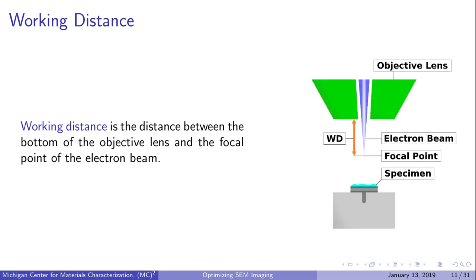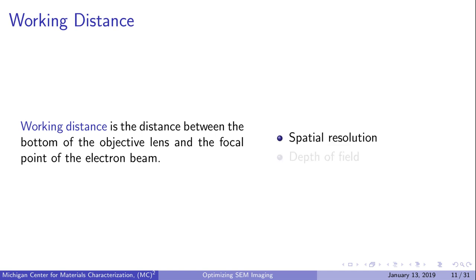The first imaging parameter we'll discuss is working distance (WD), which is the distance between the bottom of the objective lens and the focal point. When your sample is in focus, working distance becomes equivalent to the distance between the objective lens and the sample surface. Using a smaller working distance increases spatial resolution, making images appear sharper and more detailed. Working distance also affects depth of field—with a larger working distance, more of your sample surface is in focus, but the focus isn't as sharp. If your sample has large topographical features, you may want to use a larger working distance so features of different heights are in focus.